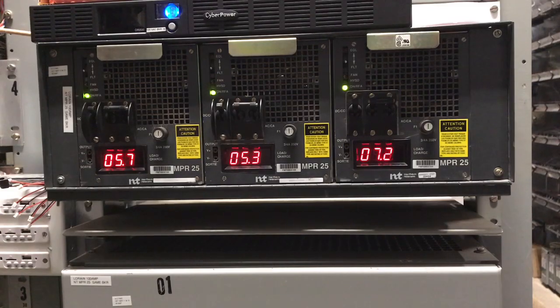With the rectifiers wired in parallel with the batteries, there's no fusing between the rectifiers and the batteries. The rectifiers have an internal fuse, but between the bus of the rectifier shelf and the batteries, there's no fusing. This is exactly how it's done in a conventional Bell and independent CO.